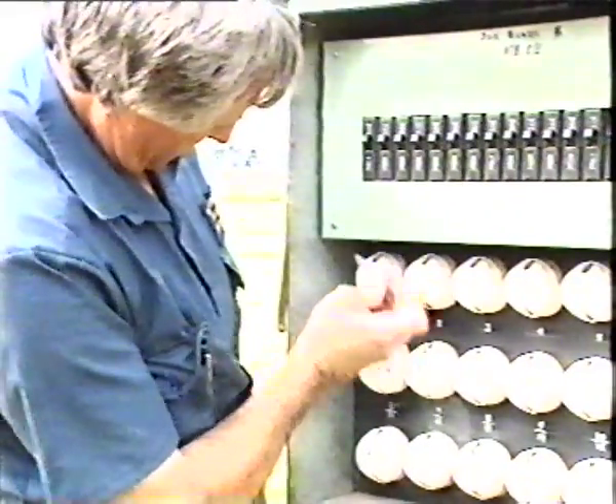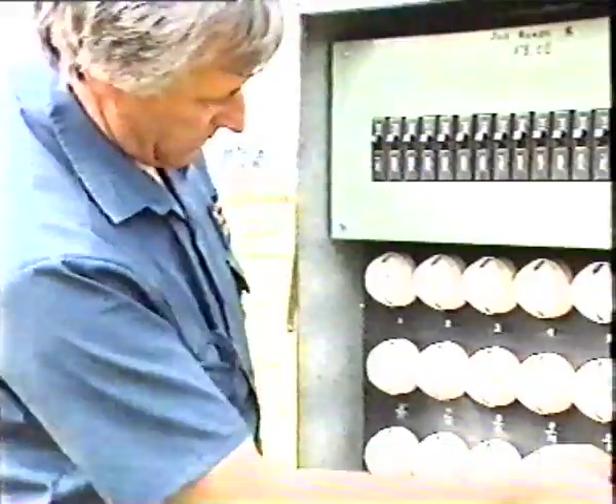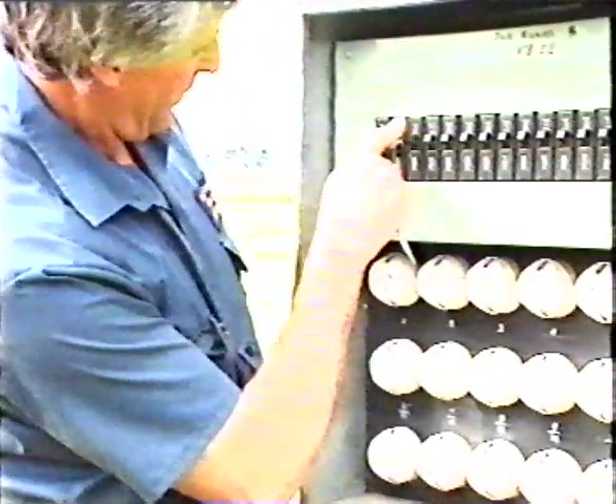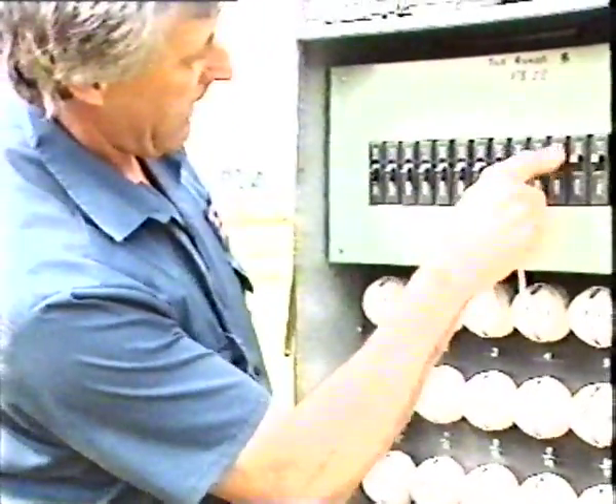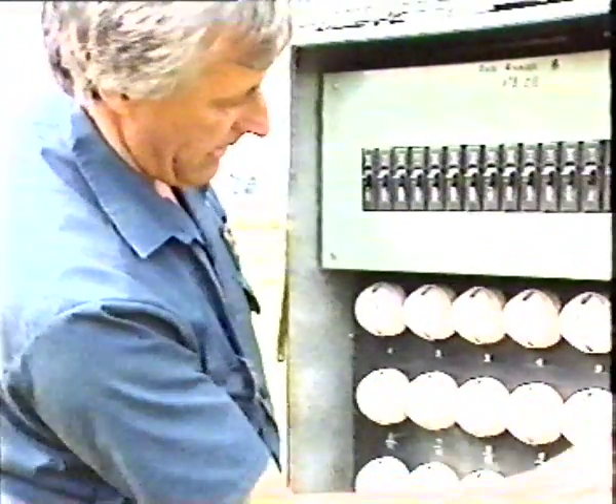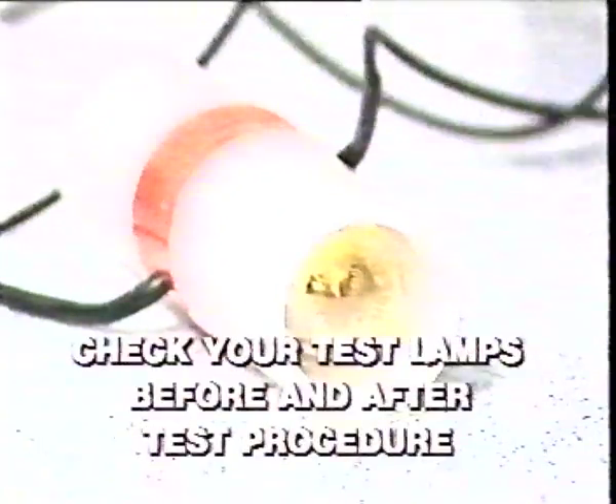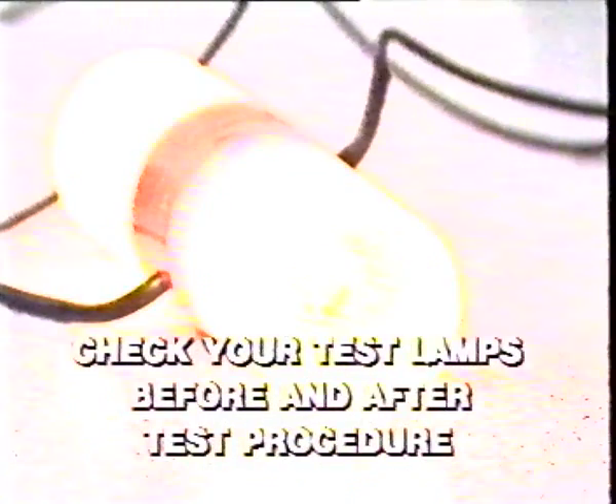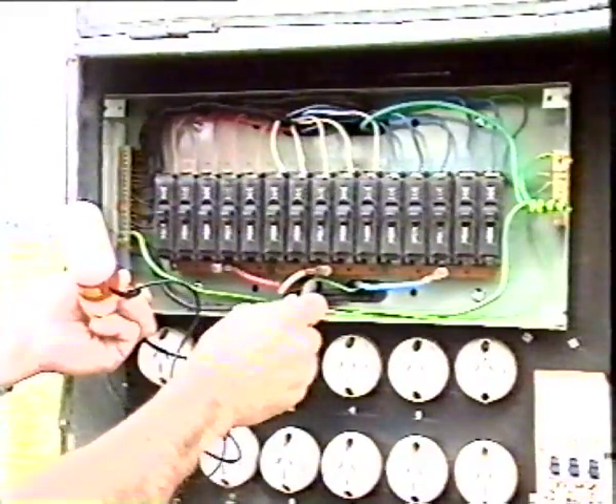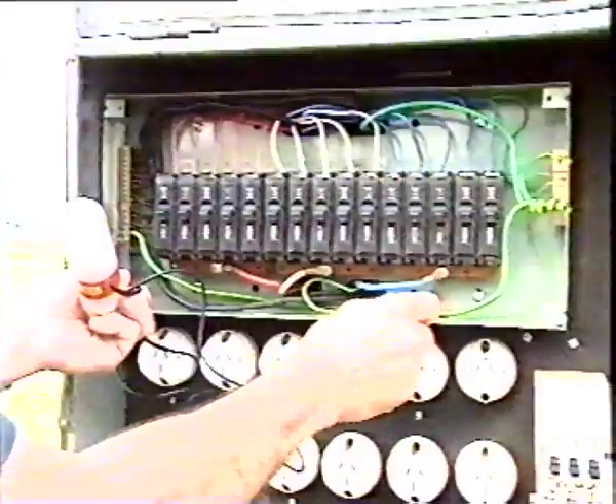Prove that the exposed metal enclosure of the distribution board is dead with a neon test probe. Disconnect the outgoing circuit active conductors, usually by opening the protective devices. Again, ensure that your lamps are working correctly before and after the test. Prove that the live parts of the distribution board are dead with test lamps from active to neutral and active to earth. Disconnect the sub-main neutral conductor and the main earthing conductor from the distribution board neutral link MEN connection.